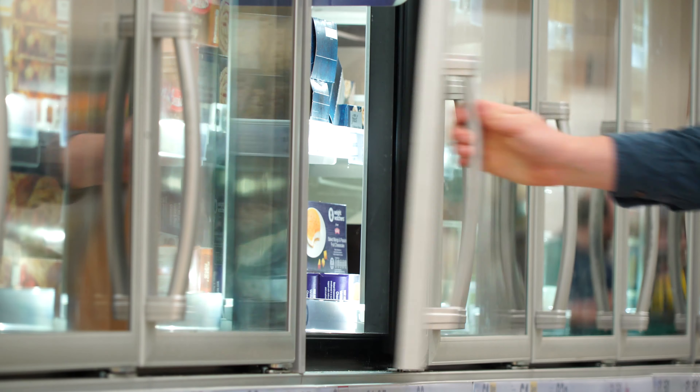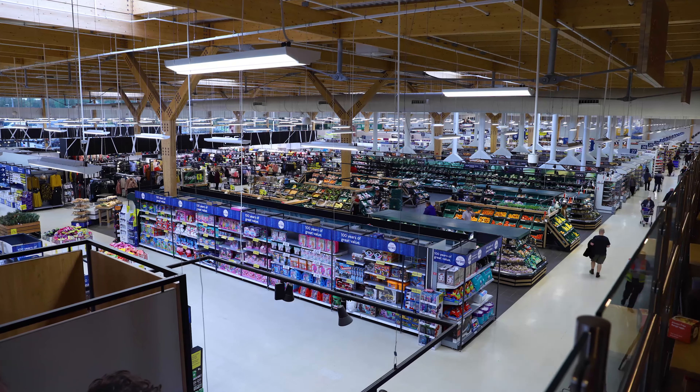You take the data from that defrost cycle, and from the rate of temperature change when you turn it off, you know the thermal inertia. If the temperature changes very slowly, there's high inertia, and those are the fridges you want to turn off during a demand-side response event.